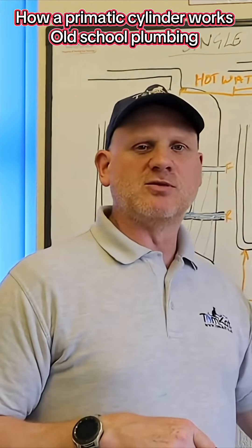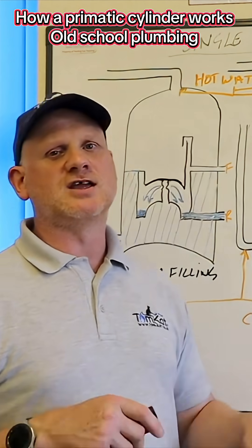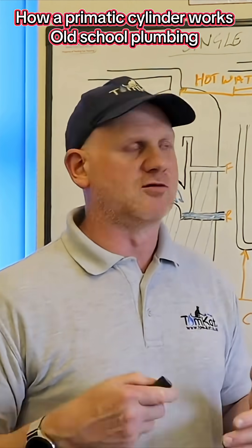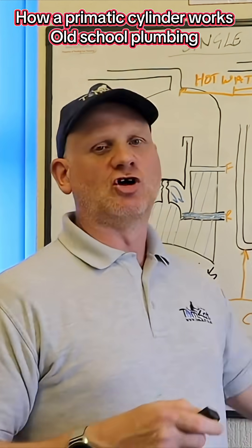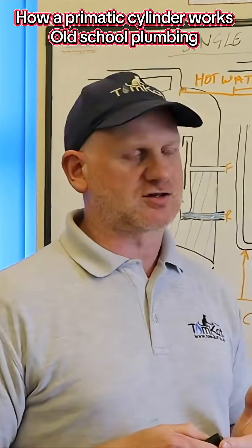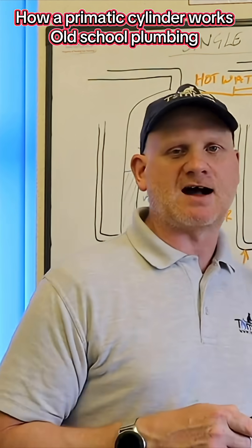So it would force the water around the gravity circuits. You cannot do that with a primatic cylinder. If you try and pump a primatic cylinder, you will break the bubble. It will be useless.